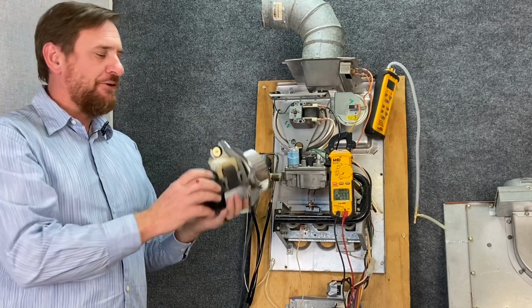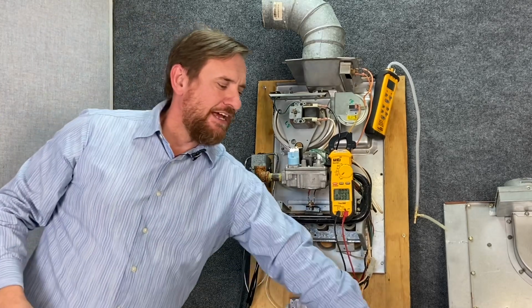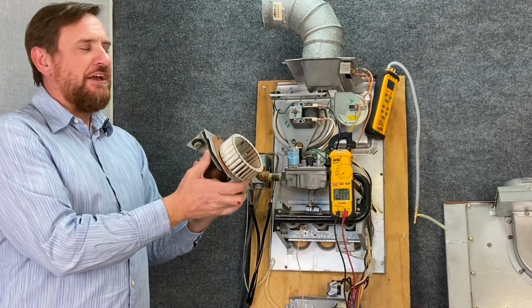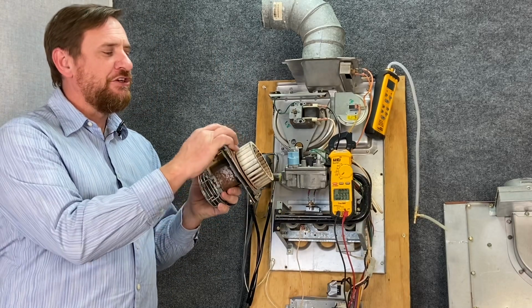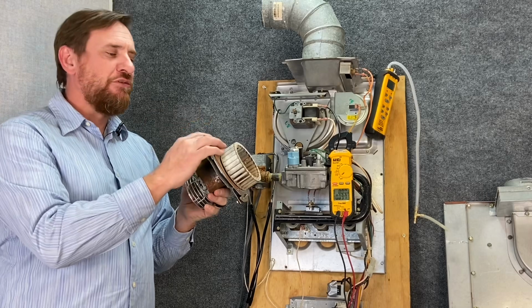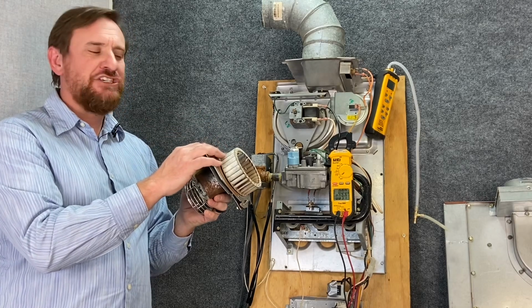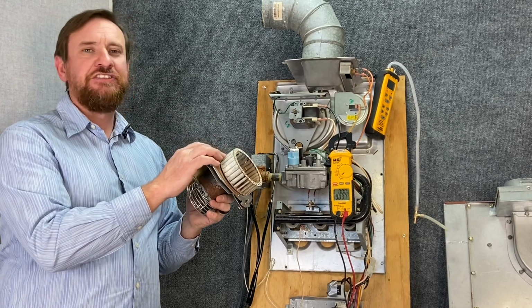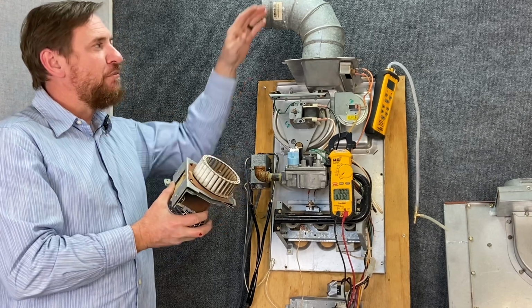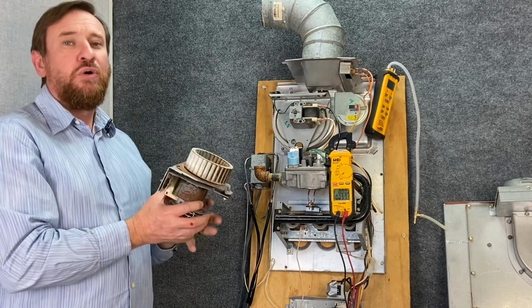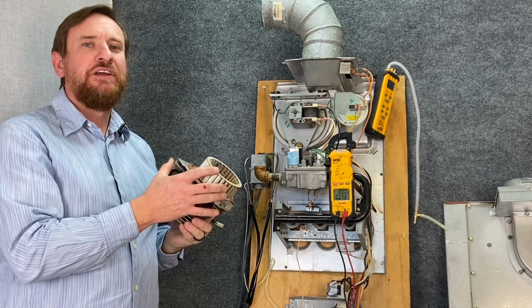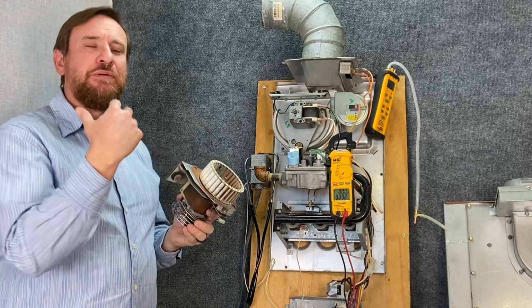Very simple little motor, but if we take a look at the same exact motor under different conditions, we see there's a good amount of corrosion on here. This corrosion is very important for us to see as technicians. If we see this corrosion, it tells us that we have one of two problems. Either we have moisture coming in through the flue pipe, or even worse, we don't have the proper combustion analysis going on. We don't have the proper amount of combustion.